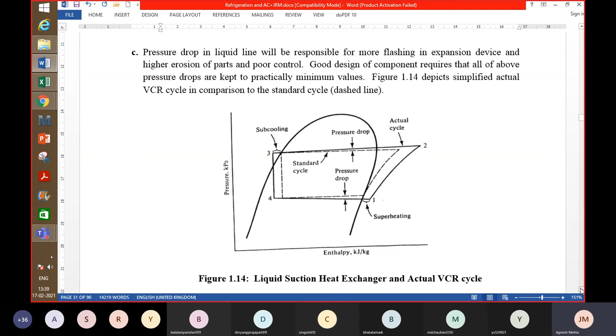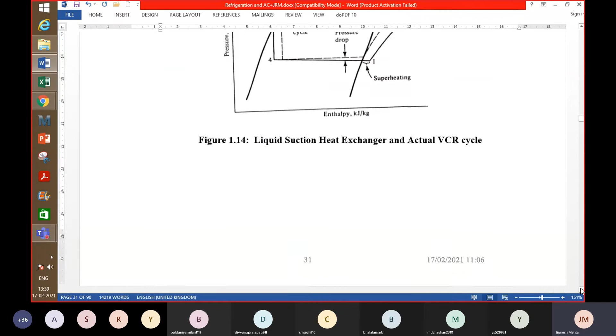So in a simplified way, you've shown the effect of the pressure drops, and obviously you can see that the area inside the cycle has increased, and because of that you are doing more work. That is about the TS diagram. But in the case of the p-h diagram, you have increased delta H across 1 2, and you may or may not have increased the cooling provided in process 4 1, because this superheating may occur even outside the evaporator, and then it is of no use for increasing the COP, right? So the actual cycle will generally provide you less COP as compared to the theoretical cycle. So this is about the pressure drops occurring in the system.